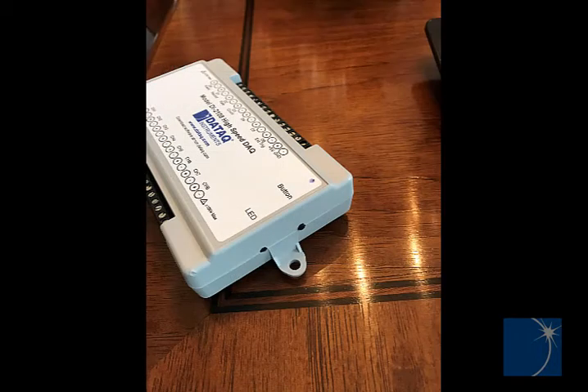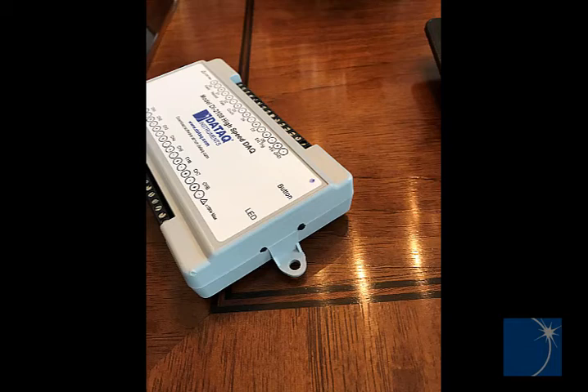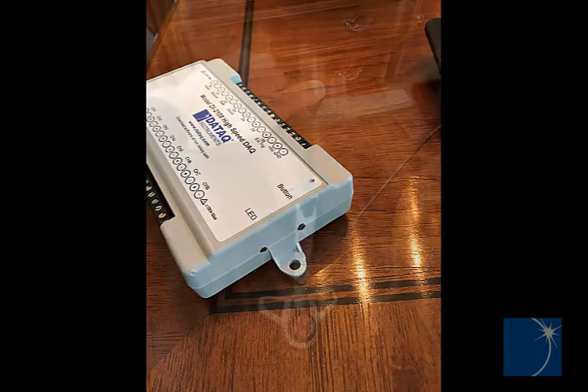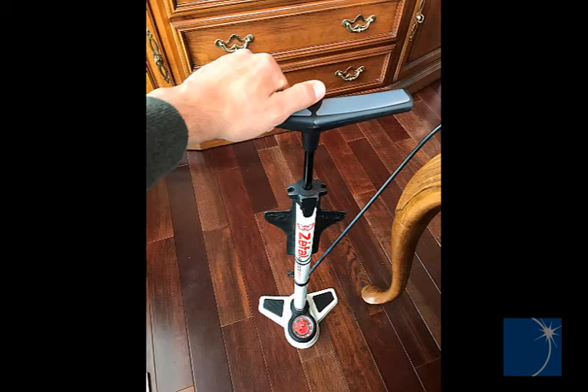With the DI2108P disconnected from the PC and powered using the AC power adapter, we'll press the push button on the side of the unit to initiate the recording and apply pressure to the transducer.